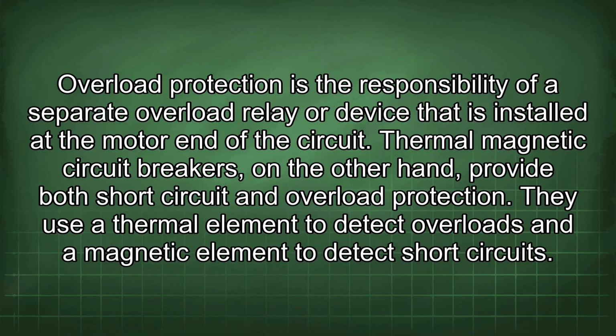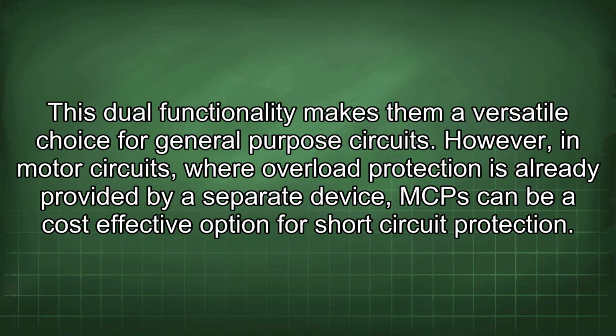Thermomagnetic circuit breakers, on the other hand, provide both short circuit and overload protection. They use a thermal element to detect overloads and a magnetic element to detect short circuits. This dual functionality makes them a versatile choice for general-purpose circuits.